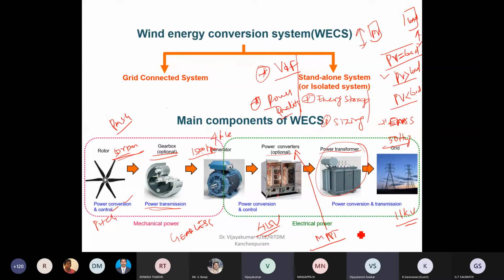Isolation, right? Isolation. Because of this isolation, it's magnetically coupled, not electrically coupled. So if there's any fault in the grid, it won't affect the turbine that much, or if there's any fault in the wind turbine, it won't pass into the grid. This provides isolation.